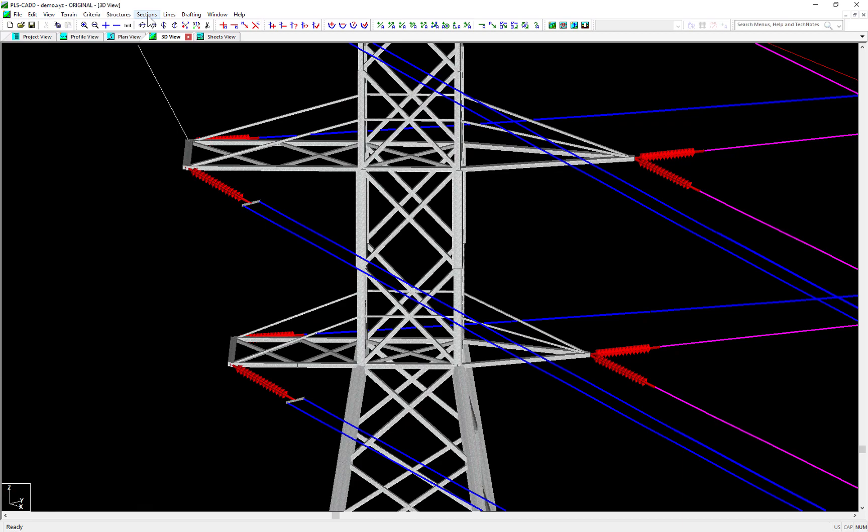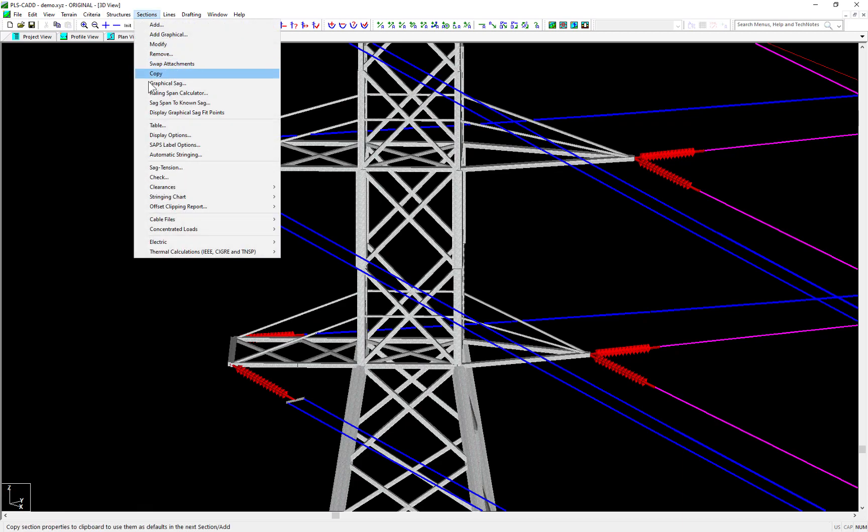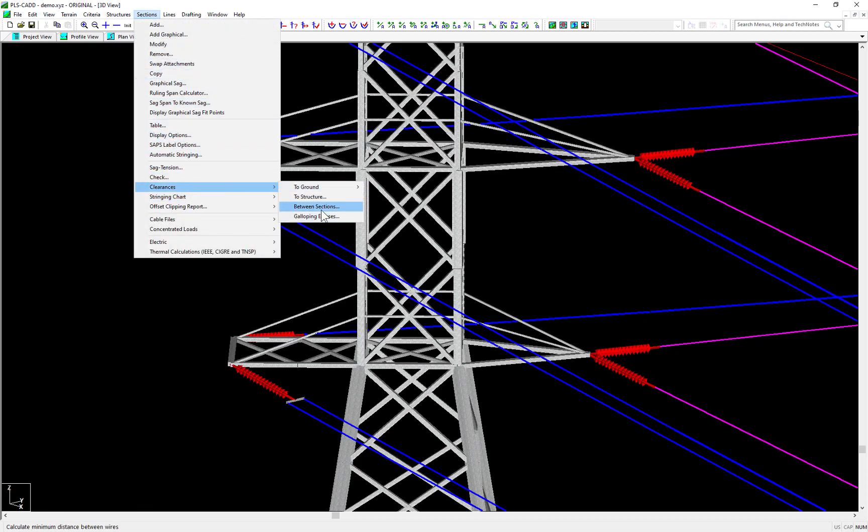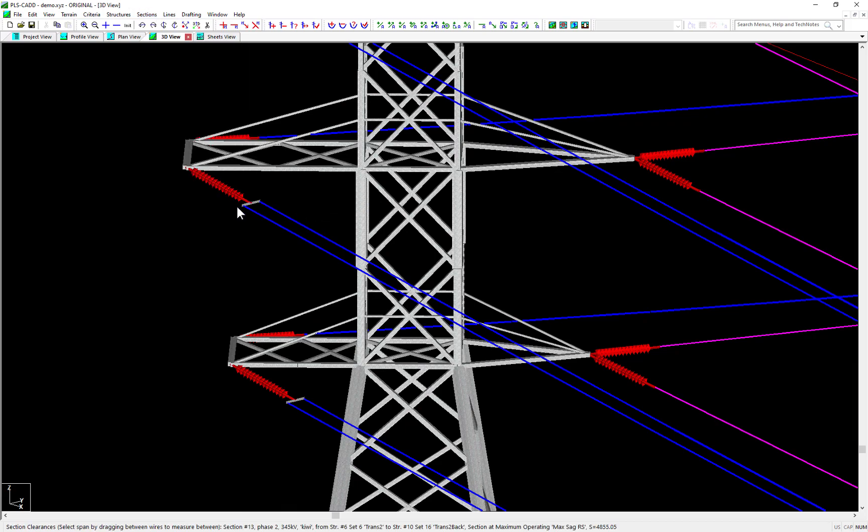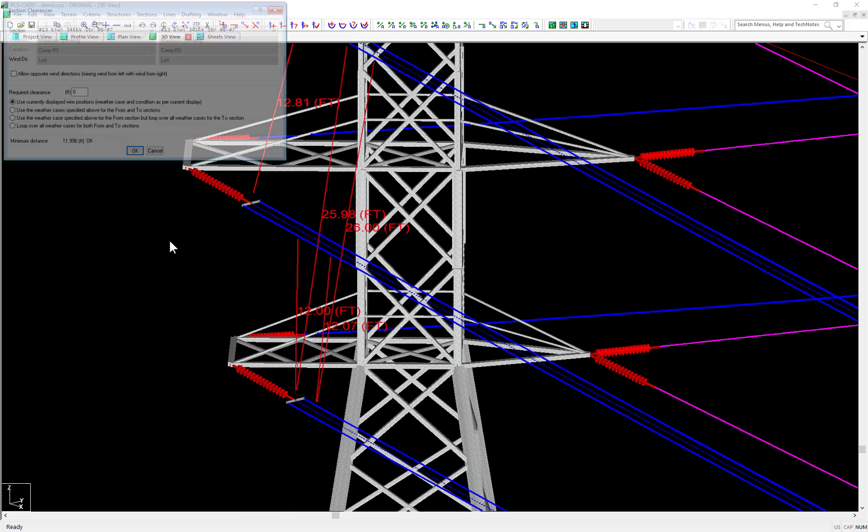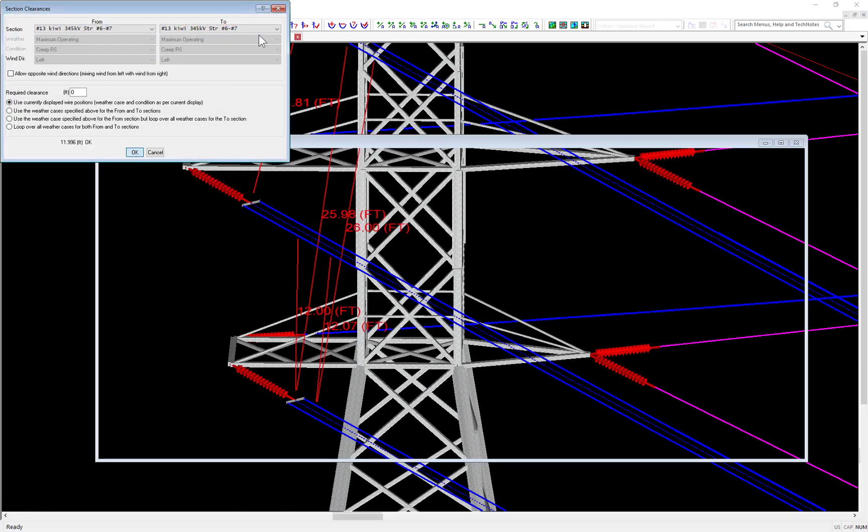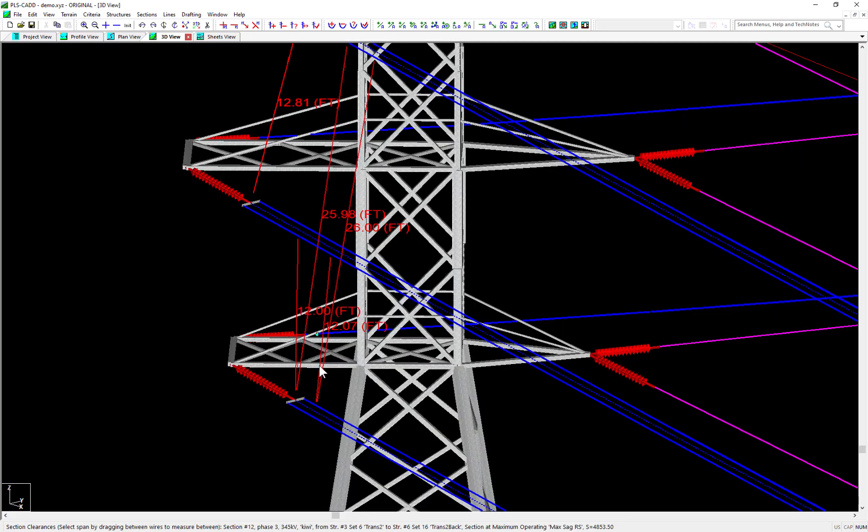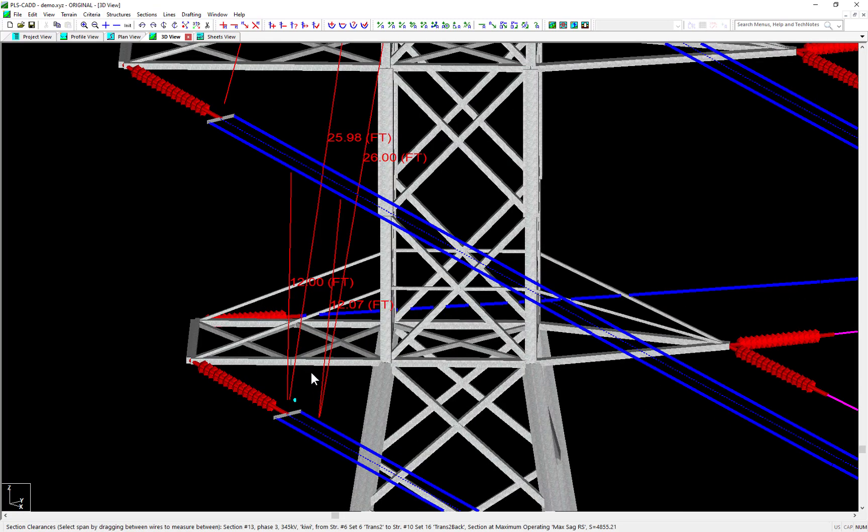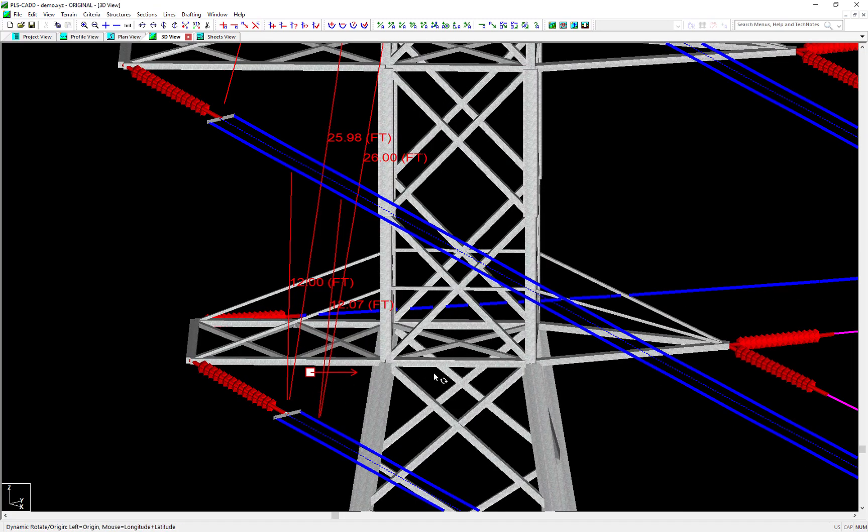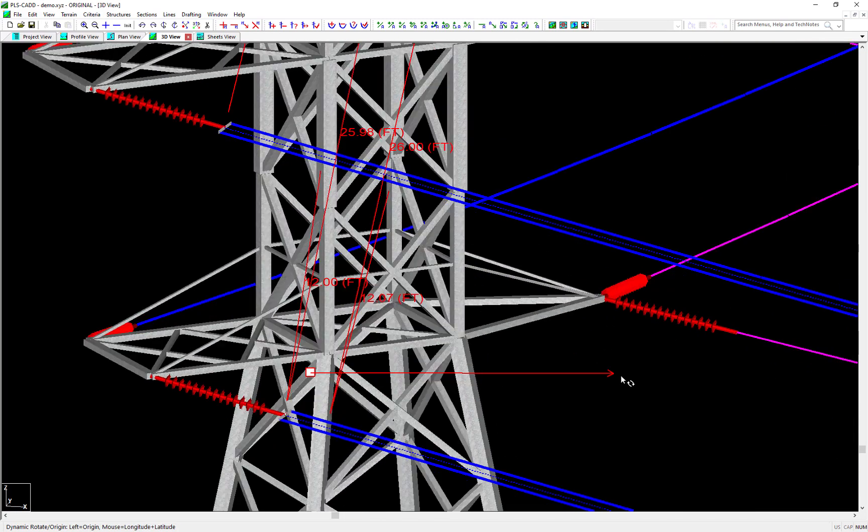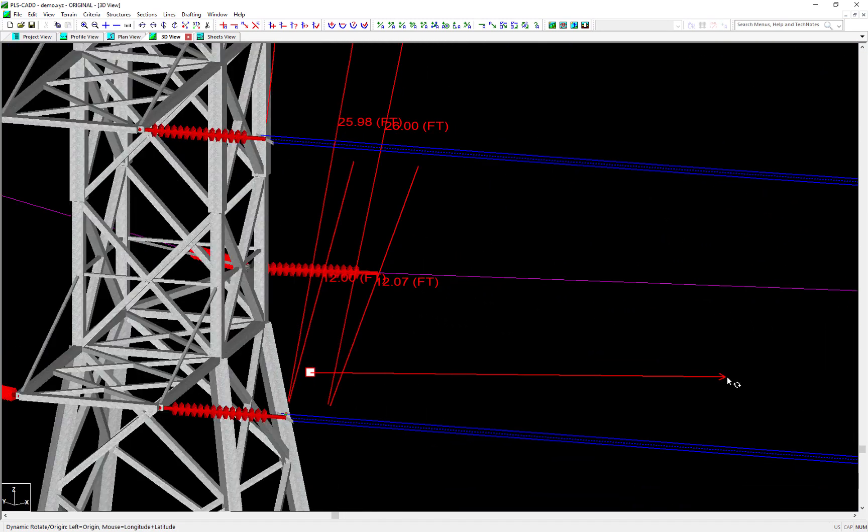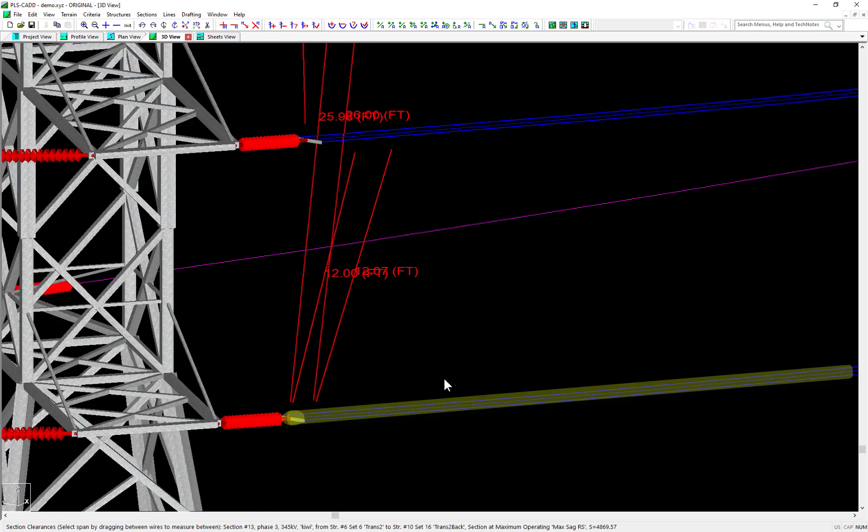Take, for example, a wire to wire clearance check using a two bundle configuration with 18 inches of spacing. Notice how after the report is ran, the graphical markers show how PLSCAD checks the clearance between two wires assuming a circumscribed circle around the bundled centroid of a diameter of 1.5 feet.